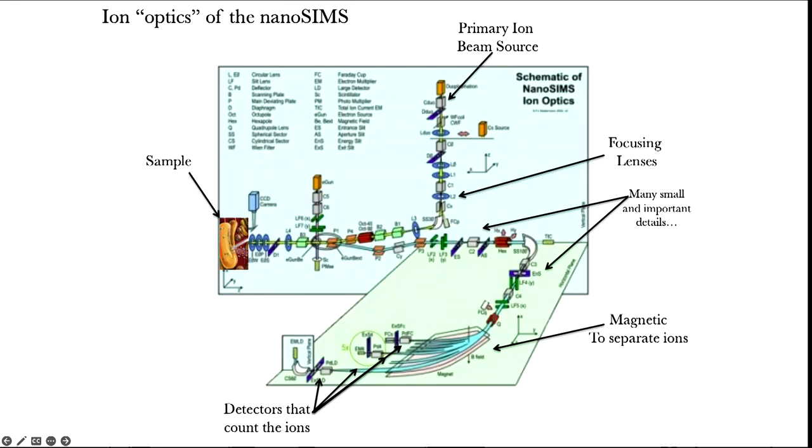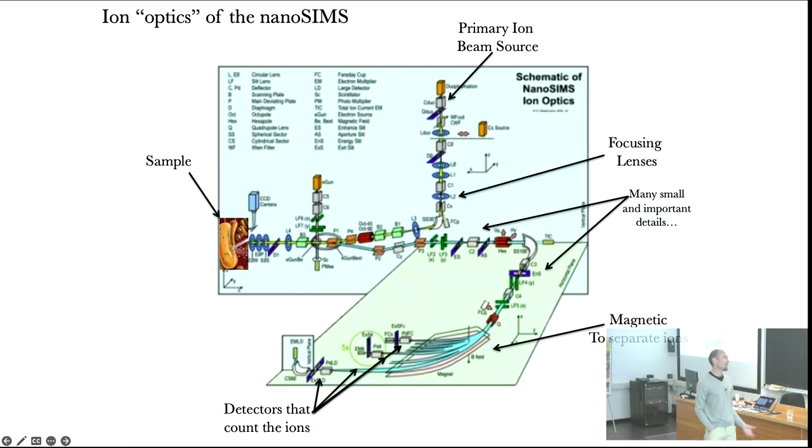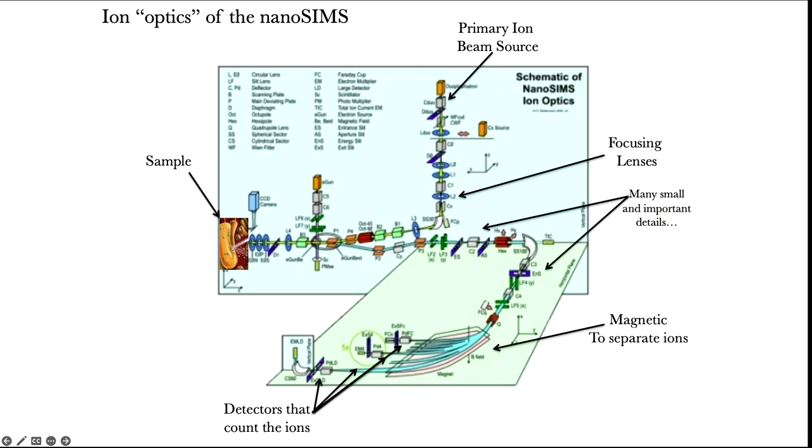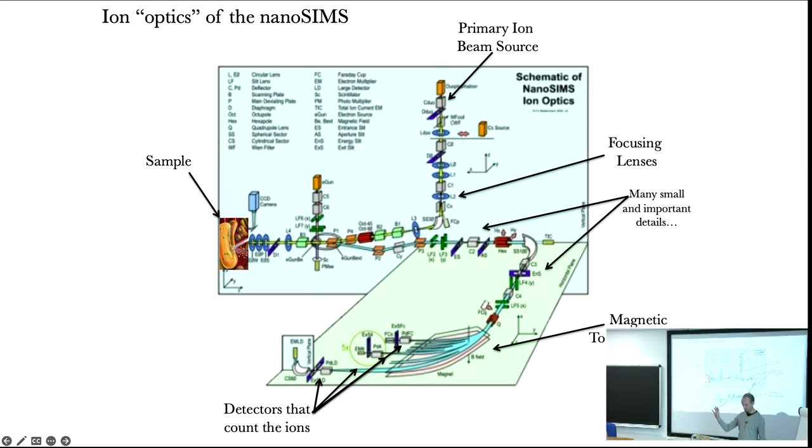Great. That's purely logistical. I'm sorry, this diagram is really kind of junky, but it's the one that Cameca makes. It's actually good because it's got all of the details in it. You've got your secondary ion beam coming out here on the bottom, going to the right, and that's getting focused. And here's your big magnet down here. It's a big black magnet. The only thing that limits you is how many trolleys, how many Faraday cups you can put in there. How much of an arc is available to you? It's completely instrumental to design.